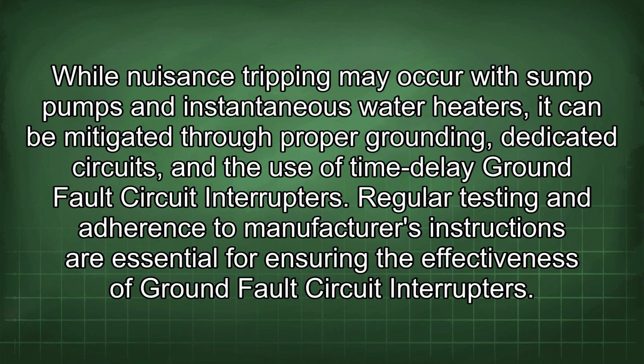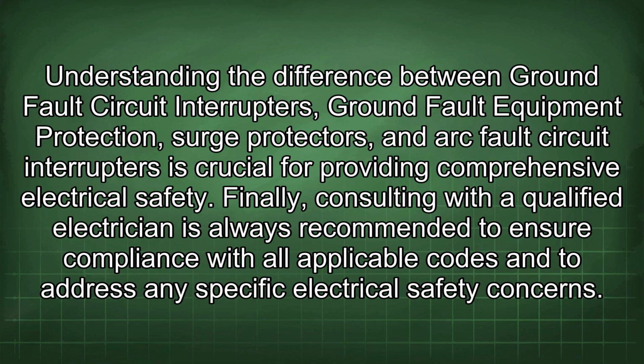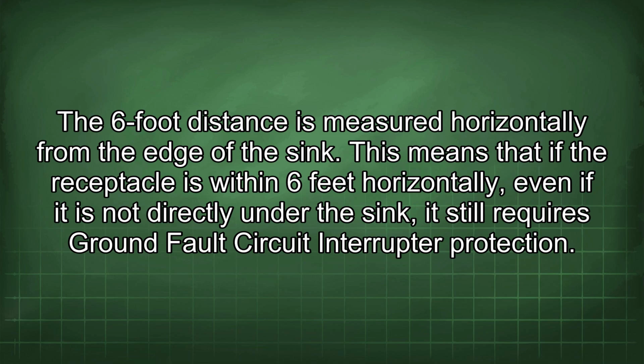Regular testing and adherence to manufacturers' instructions are essential for ensuring the effectiveness of ground fault circuit interrupters. Understanding the difference between ground fault circuit interrupters, ground fault equipment protection, surge protectors, and arc fault circuit interrupters is crucial for providing comprehensive electrical safety. Finally, consulting with a qualified electrician is always recommended to ensure compliance with all applicable codes and to address any specific electrical safety concerns. The 6-foot distance is measured horizontally from the edge of the sink.